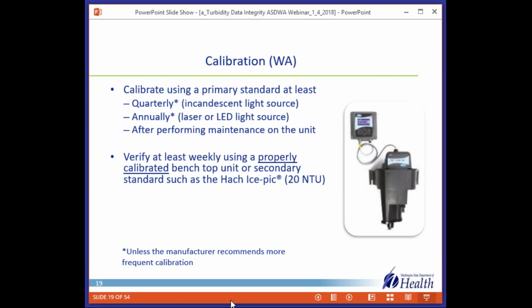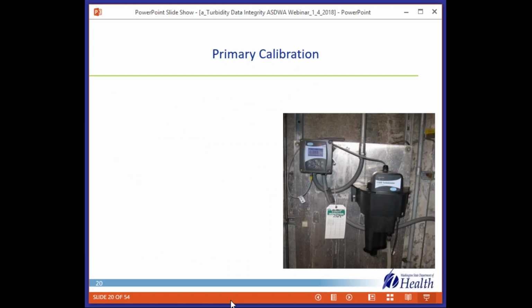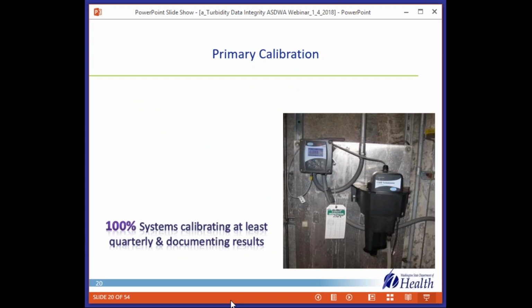In addition, continuous online instruments have to be verified at least weekly using a properly calibrated benchtop unit or a secondary standard such as the Hach Ice-pic 20 NTU. So looking at primary calibration, 100% of the systems were calibrating at least quarterly and documenting the results.